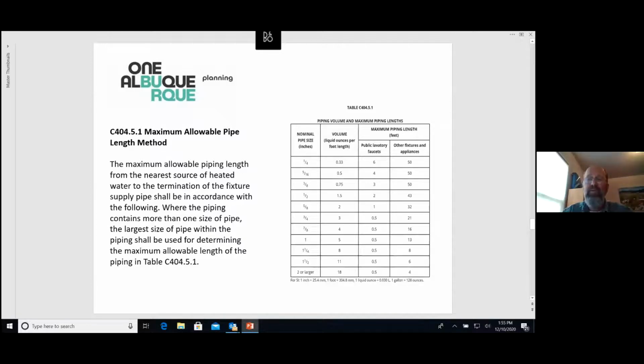Other fixtures, you've got a much greater distance, and this chart demonstrates some of the lengths and distances. The larger the pipe, the shorter the distance, because you've got more volume you've got to remove the untempered water out of. And this goes up to the point of distribution, which is your angle stop in essence.